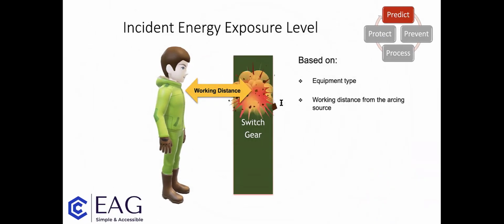Quickly, then, the incident energy exposure level is measured to the person stood in front of a prospective arc, to his face and his torso. It depends on the equipment type, and also on the working distance from the arcing source, which alters depending on what you're actually doing to the equipment itself.